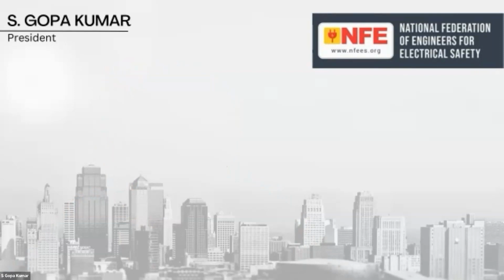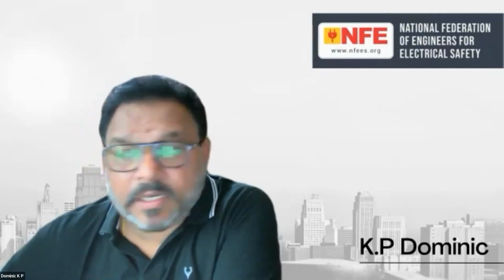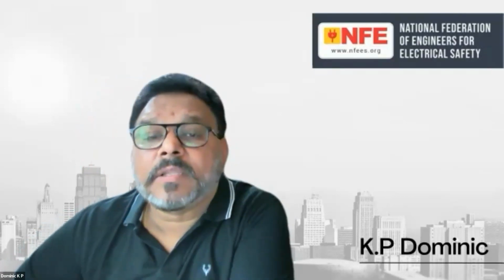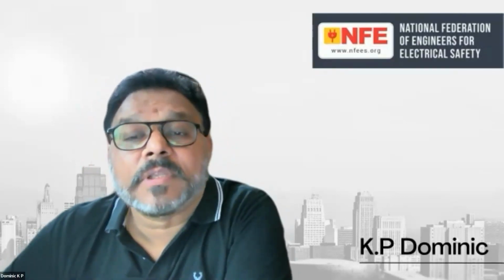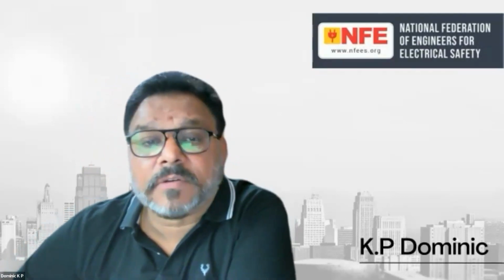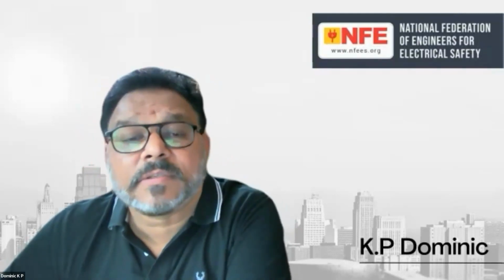Structural engineers are now accepting it. Now, for your information, the distance of 3 meters from the down conductor is applicable if you go for an exposed lightning protection, that means an external lightning protection. Badresh has been designing a lot of tall buildings in Bangalore, so I'm sure this is a very relevant question that he's asking, to apply to the buildings he's designing.